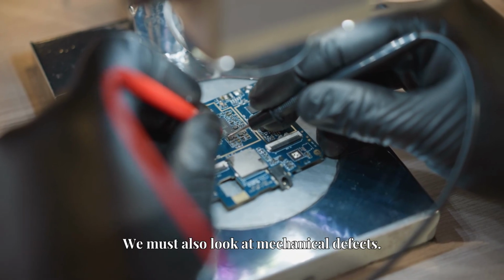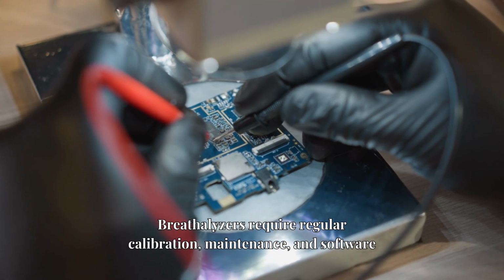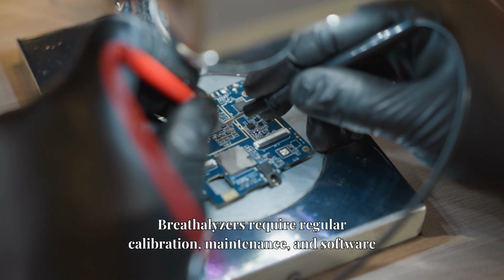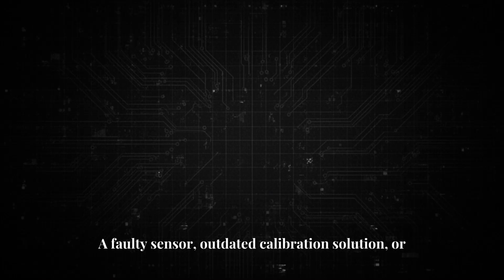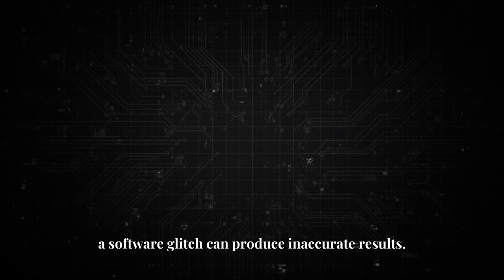We must also look at mechanical defects. Breathalyzers require regular calibration, maintenance, and software updates. A faulty sensor, outdated calibration solution, or a software glitch can produce inaccurate results. Even small amounts of residue from prior tests can skew a reading.